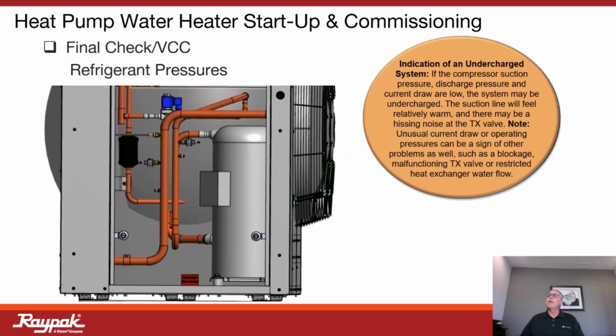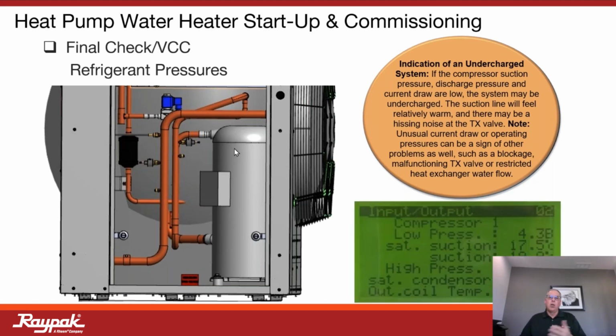So I think this is also very helpful on a startup and commissioning to demystify the process, remove the intimidation factor, and say, we have a refrigerant, we don't have to interact with it physically, but we can go in and note what those refrigerant pressures and temperatures are in terms of that startup and commissioning process. I think this is also very helpful in understanding what we're doing and what normal operation will look like. So also, if I have an undercharged system, if I've lost refrigerant somehow, how's that going to manifest itself? And we can again look for those temperatures and pressures in that system, note it on our startup and commissioning, and make this process very simple and straightforward.